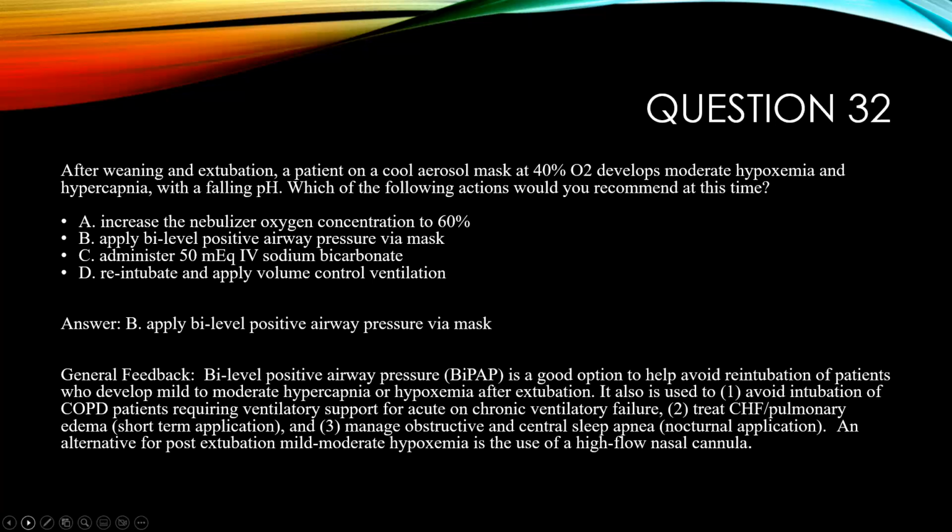Many of the latest generation invasive ventilators can do BiPAP. The trick there is to convert them over. It's going to take at least a few minutes to get the machine into the mode once the patient's extubated, and get the mask set up and things along those lines. But besides that, you may not need a new device. In many cases, you can just use the invasive ventilator that you had. Just best not to wait too long.